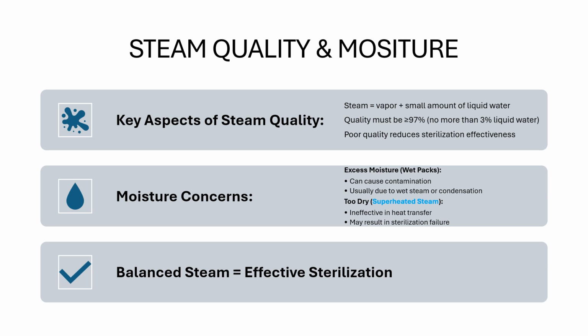Superheated steam. This is where steam is too dry and it cannot transfer heat effectively, which may result in sterilization failure. So if it's way too dry, that steam's not going to come in contact with the devices during that contact time. And remember, we need that contact time. So if moisture's not on the items, then it's not doing its job. So we don't like dry heat. We don't like superheated steam. So maintaining the right balance of steam and moisture ensures sterilization efficiency and the patient's safety.